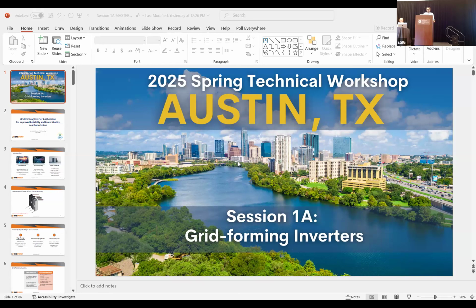In general, in Tesla grid forming, the inverters respond on a sub-cycle basis to maintain the voltage and frequency references received from the Tesla site controller. In summary, the power dispatcher path, which acts on the left-hand side in the picture as a current source, can achieve things like peak active and reactive power dispatch, frequency market participation, plant level voltage control, etc. On the other hand, the virtual machine path, which acts as a rotating machine, can achieve things like inertia power responses, phase jump power responses, black starting, and increasing the system strength.